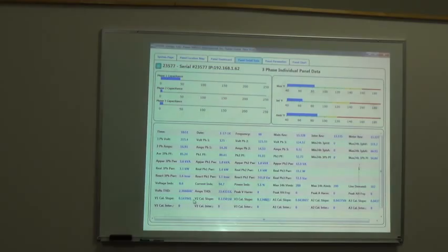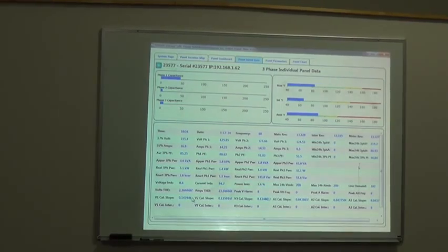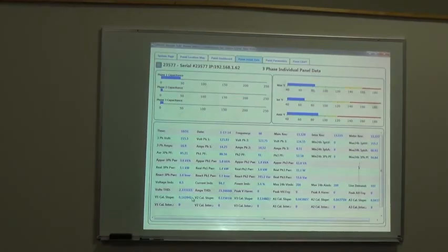For the calibration, you don't have to display that though. Oh no, you do have to display it. That's the difference. You have to, because if I want to physically change the value of the calibration - and there is a way, this isn't something you want to tell your customer, but I'll tell you how - right through the spider you can calibrate now, okay? But basically, you do need all the 5, 6 digits.